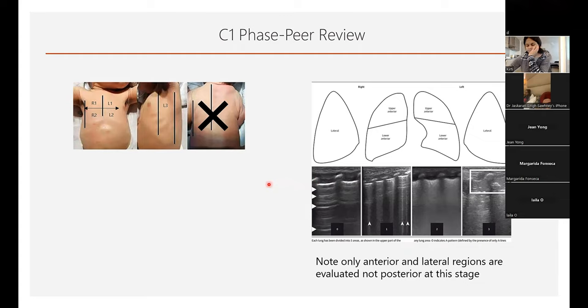There are machines which have auto gain settings. Auto gain basically adjusts the background gain. Now, there is spatial gain and there is gain that is transverse gain—each machine is different. In our machine, on the GE, we use transverse gain. And I would say to you that you can use auto gain functions, but sometimes the auto gain function, if your probe is not in good contact, kind of defaults to settings which might not be optimum.